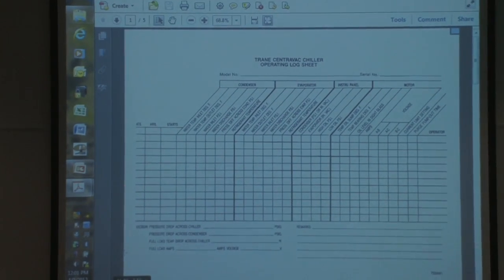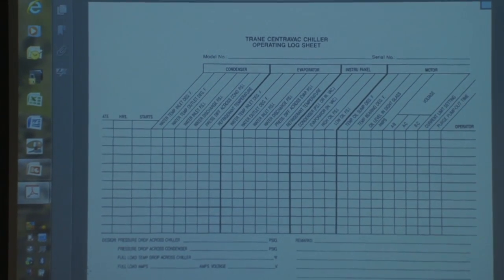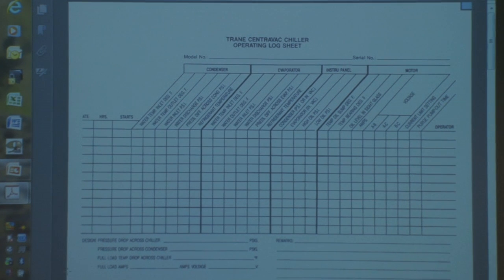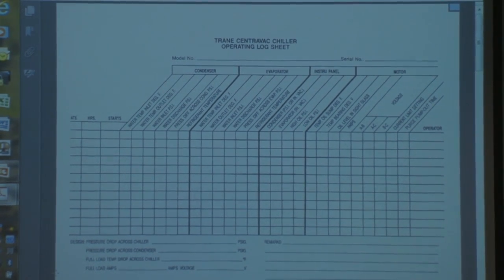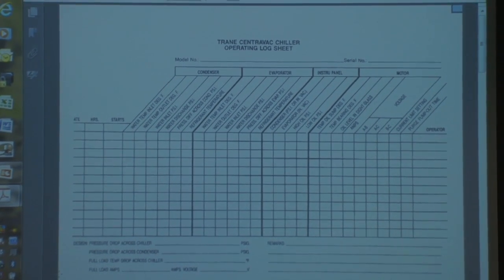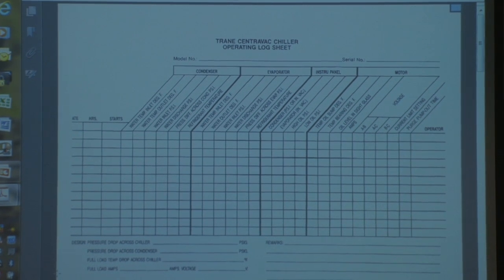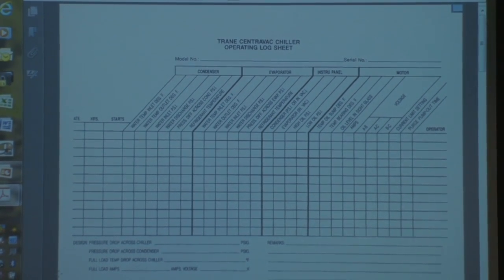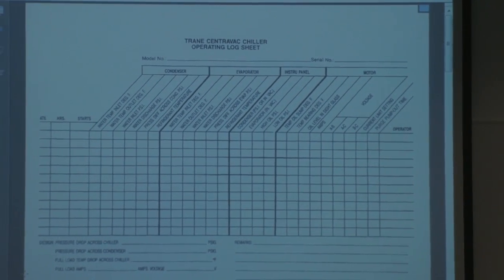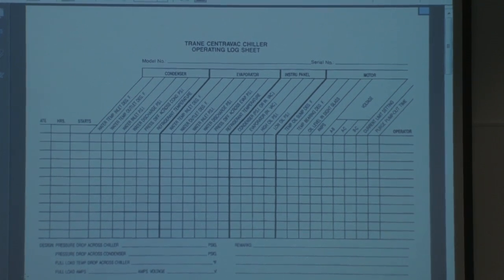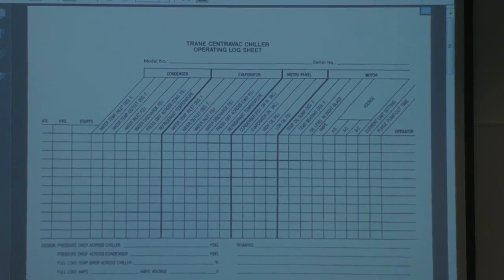See if my laser pointer works. There we go. Having the time too is good. You want to pick the same time every day, ideally, or around the same time. So if you start logging in the afternoons, which might be a good time to do it, mid-afternoon, log it every mid-afternoon. Nothing's wrong with logging it in the morning, mid-morning, and in mid-afternoon. You actually may see two different readings depending on how it's loaded.